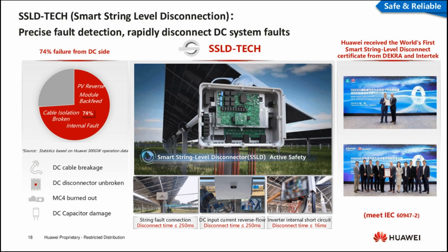DC side faults are frequent in PV plants, and what is important is to have a technology that would rapidly disconnect the system before the fault and the hazards propagate. Such technology brings the smart controller as a key system component for active safety. Various situations like string fault connection, DC input current reverse flow, and internal faults that can also happen are all well addressed through this smart string level disconnection feature that is integrated into the products.